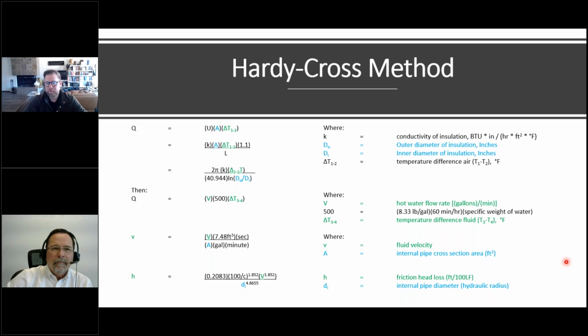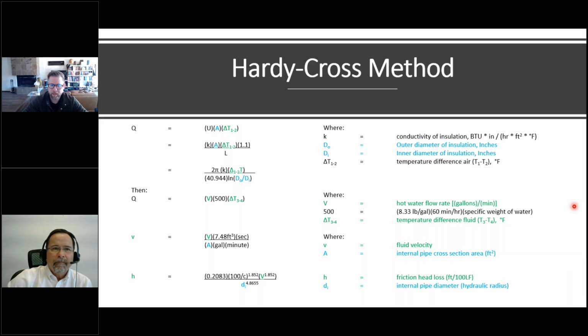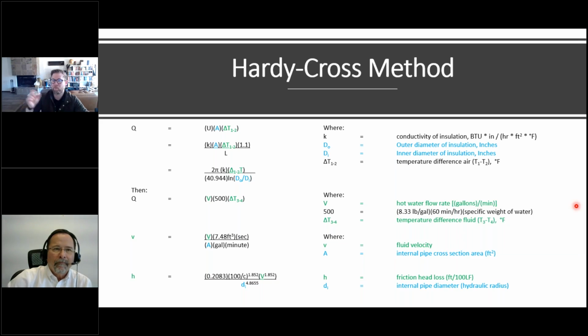Yeah, so in the ASPE Legionella task group that created that design guide, that again you can get through the ASPE bookstore site, we recommended actually determining the temperature drop through the supply and the return. One of the things that we recognize, especially from a waterborne pathogen standpoint, is if your return piping ends up getting in that temperature range, that can become a breeding ground. So you really want to know what your return piping temperature is from that standpoint.